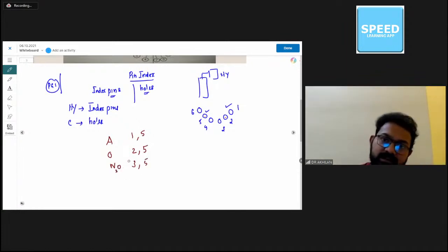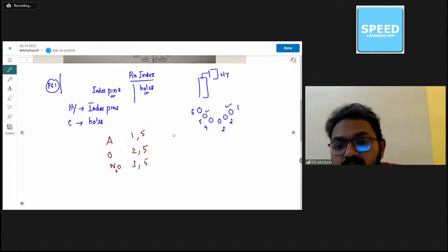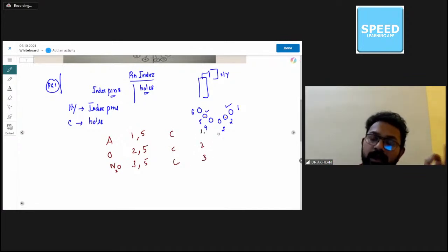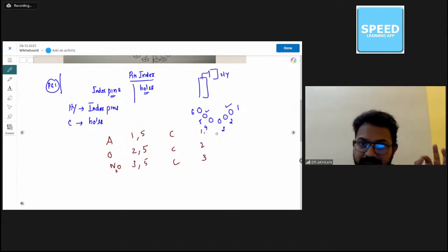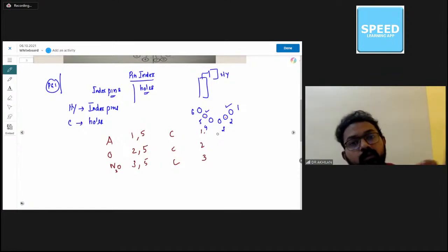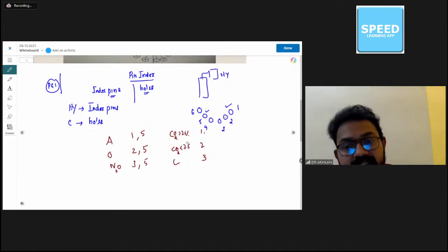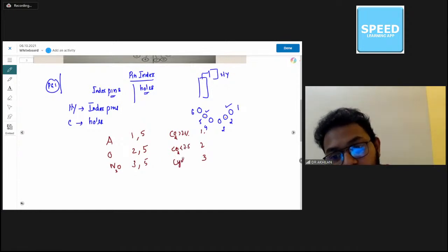Air, oxygen, nitrous oxide. Similarly, also remember C, 1, 2, 3. You remembered AON 1, 2, 3. Air is 1,5, oxygen is 2,5, and nitrous oxide is 3,5. Learning done. Now remember one more important code, C, 1, 2, 3. What is C? Carbon dioxide more than 7.5%. What is next C? Again, carbon dioxide less than 7.5%. And what is 3? Cyclopropane.